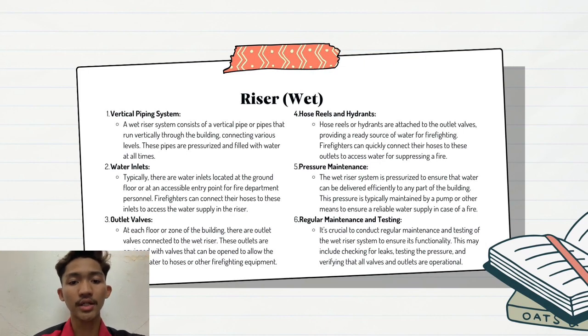Fifth, pressure maintenance. The wet riser system is pressurized to ensure that water can be delivered efficiently to any part of the building. The pressure is typically maintained by a pump or other means to ensure a reliable water supply in case of a fire. Sixth, regular maintenance and testing. It's crucial to conduct regular maintenance and testing of the wet riser system to ensure its functionality.